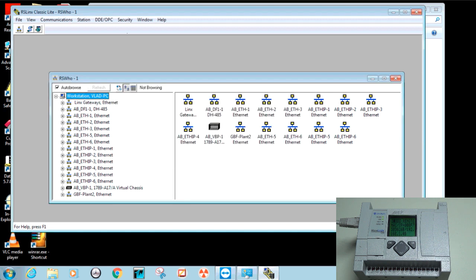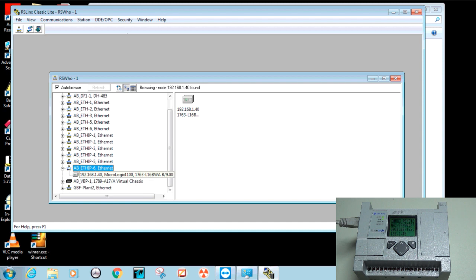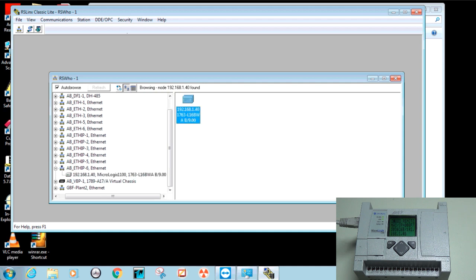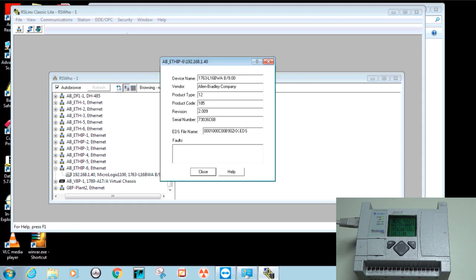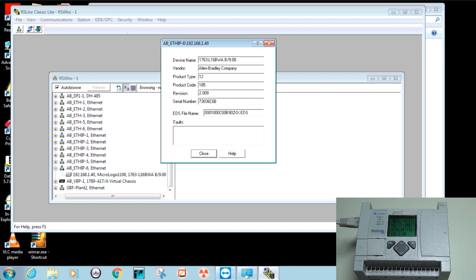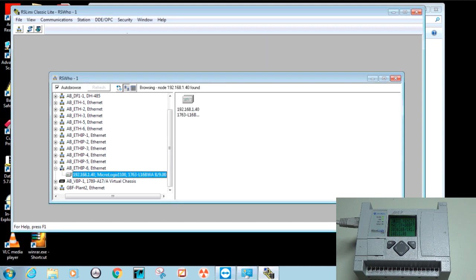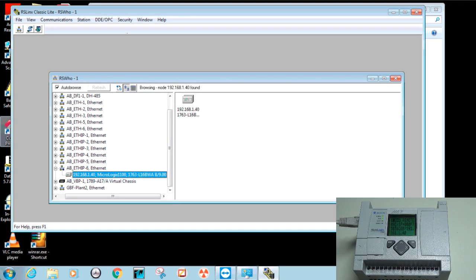Hit Close, and if everything is correct you should be able to browse and see the Micrologix at the IP address we assigned. If there is no red X on the screen, communication is good. You can right-click to see device properties — for the Micrologix you'll mainly need the revision number. If you disconnect the ethernet cable, you should see within a few seconds a red X indicating the communication path is no longer established. At this point we know proper communication is established to our controller.